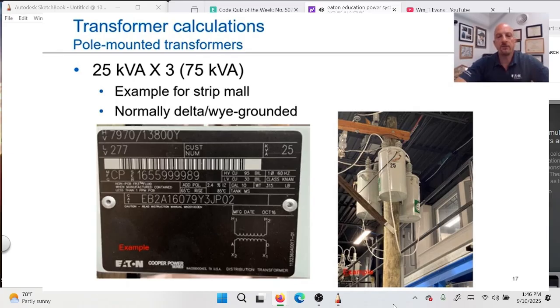And actually, if you get up close, and again, earlier I was showing you from the bridge there. If I looked at that nameplate, I could actually see the nameplate and the impedance of this transformer. In this case, it's 2.4%. What's interesting about pole mounted transformers is they do have a lower impedance. So we made an assumption earlier, if you didn't know the transformer impedance, you could say 5.75%.